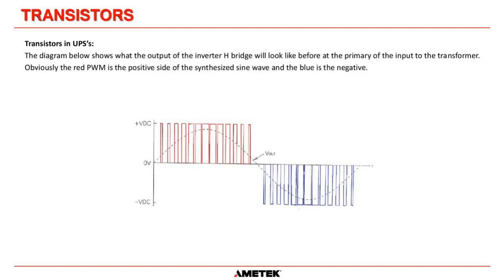Remember, this voltage here is 135 volts DC for a 60 cell system, and this voltage here is also 135 volts DC. Now, if you lose power, the batteries start supplying the inverter bridge and that voltage goes down. As that voltage drops, the advantage of PWM is we can widen all of these pulses to raise the average, maintaining the output of this system at exactly 120 volts using pulse width modulation.